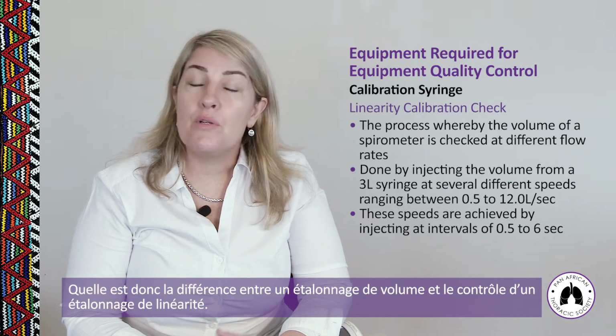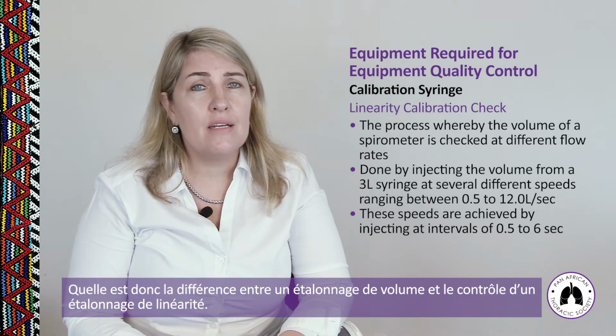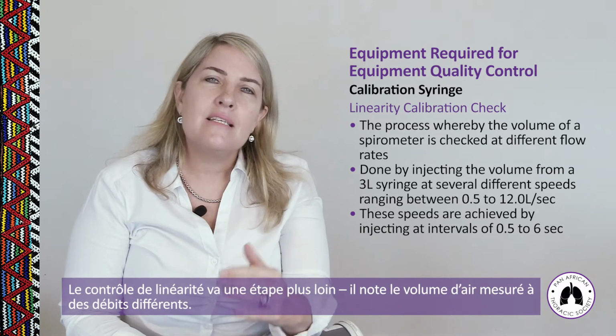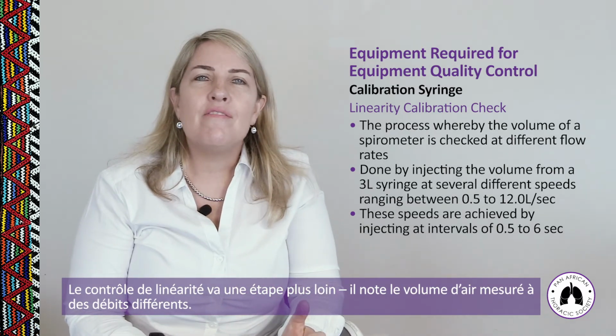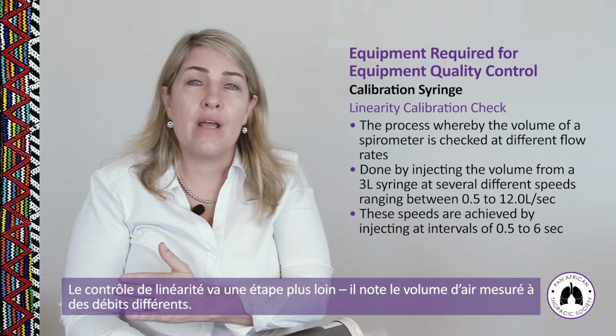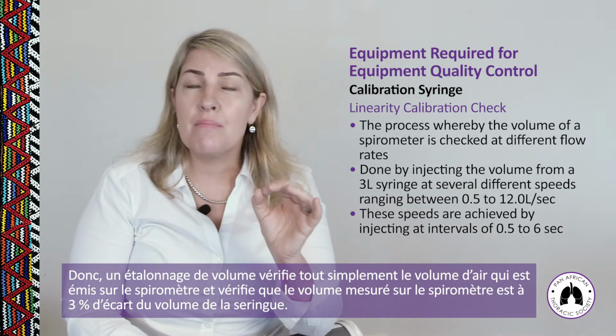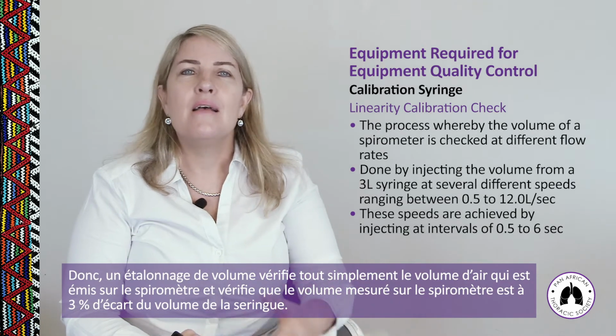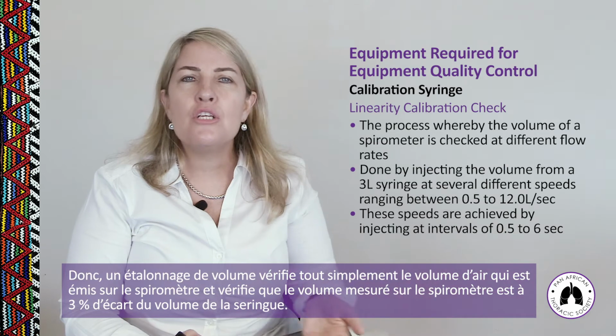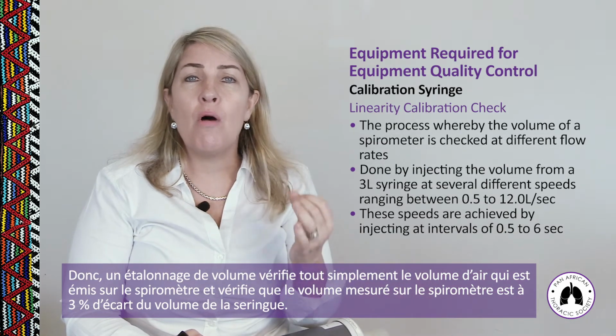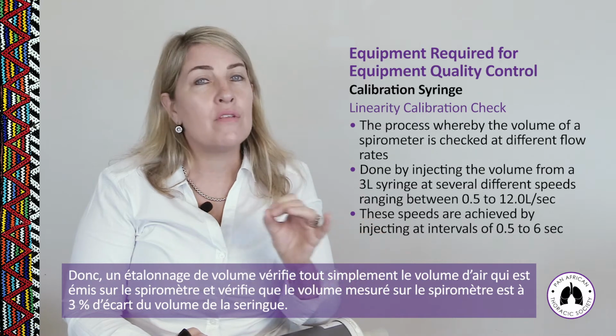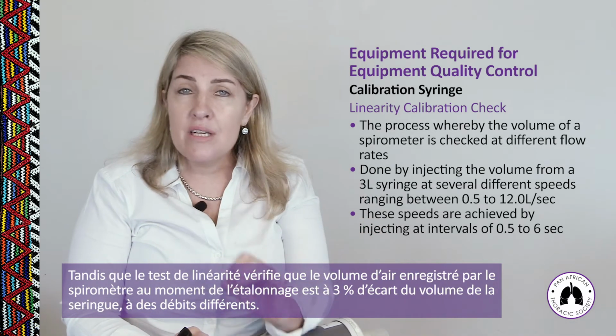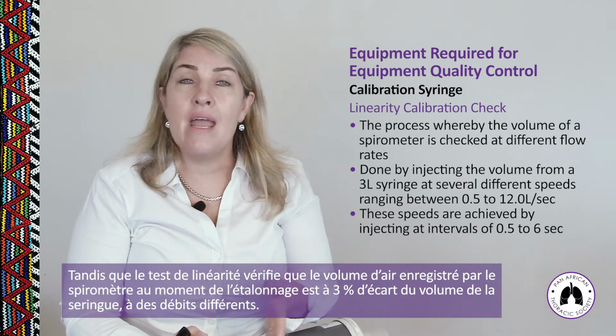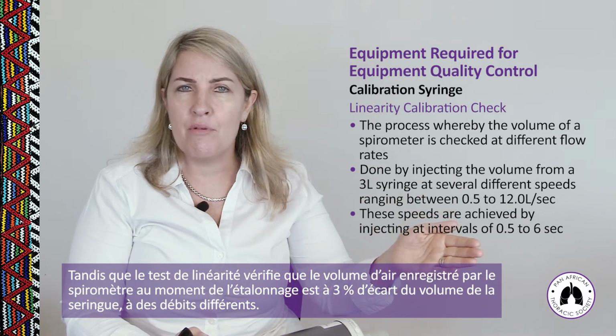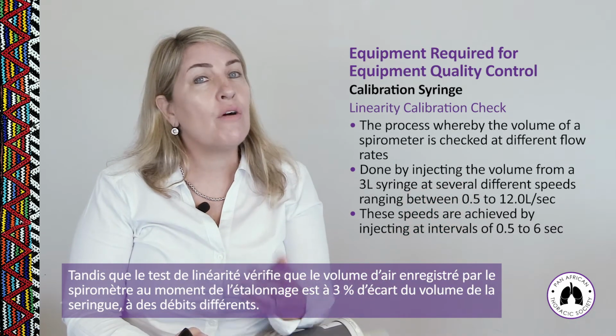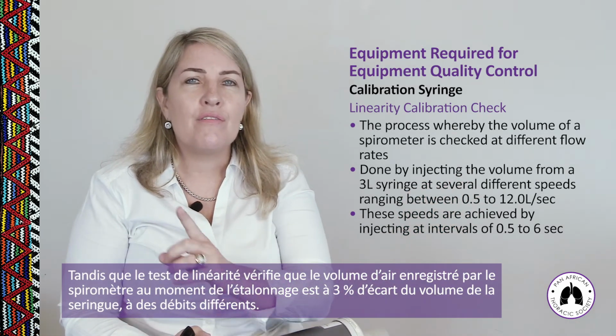Okay, so what is the difference between a volume calibration and a linearity check? So a linearity check takes things one step further. It looks at the volume of air measured at different flow rates. So a volume calibration very simply is looking at the volume of air pumped onto the spirometer and making sure that the measured volume on the spirometer is within 3% of the syringe volume. Whereas a linearity check is making sure that the volume of air read by the spirometer at the time of calibration is within 3% of the syringe volume at different flow rates.